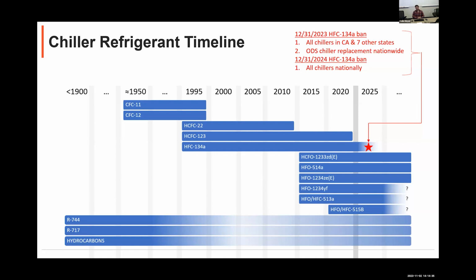Below that are some naturals. So there's R744, which is CO2, R717, which is ammonia, and then there are many hydrocarbons. Those were some of the original refrigerants in use. On the left of the chart, the middle of the chart, we kind of faded it out. They became less common when all these other synthetics were on the market. But then after the Montreal Protocol and then focus on global warming and the Kigali Amendment to the Montreal Protocol and all these next generation refrigerants, we are starting to see the natural refrigerants under consideration more, just because they're proven technology, but they do each have challenges.